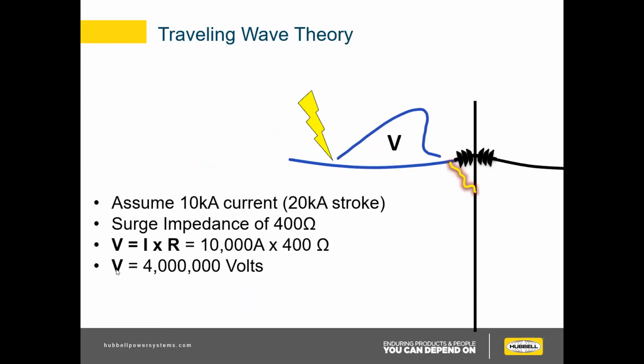So for the sake of simple math, let's say we have a 20 kA stroke. That'll divide in each direction. You have 10,000 amps going in each direction. And a normal surge impedance is 400 ohms. And you can calculate our voltage spike with this information. So 10,000 amps times 400 ohms is 4 million volts. So that's a lot. And any equipment, insulator, transformer, whatever on this line that has a basic insulation level, BIL, of less than 4,000 kV is going to flash over and be damaged. So it's pretty much always going to be destroyed.